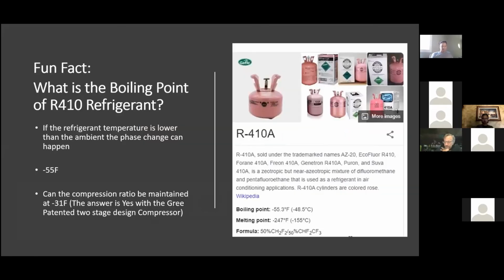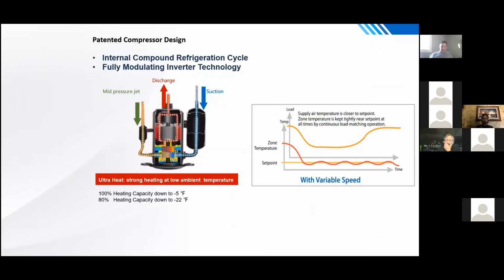Some more fun facts here. The fact that R410A boils at minus 55 is still an incredible feat in my mind, that we can use the outdoor unit as an evaporator and pull heat from it, I think is amazing. But the fact that it boils at minus 55 kind of tells the story. And you'll all have to forgive me as I muddle through this, because Gree doesn't tell us exactly how their compressor works. They give us all the ratings for it.